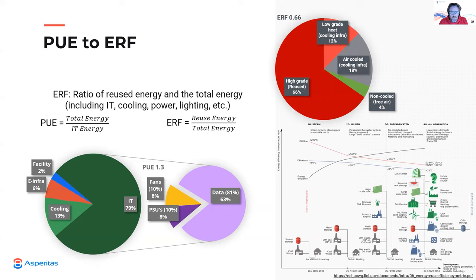The applications for such heat reuse are numerous and not limited to the heating of households. Try to search online for fourth generation heat grids. These grids are rolled out now and will gain momentum in the upcoming years across Europe. These heat grids will be able to take heat directly from facilities and distribute it across a large network of consumers. Heat reuse is important to consider because when heat is delivered, cooling is supplied in return. Therefore, reuse is cooling without spending the power or the money on expensive installations, which are only focused on getting rid of the energy.